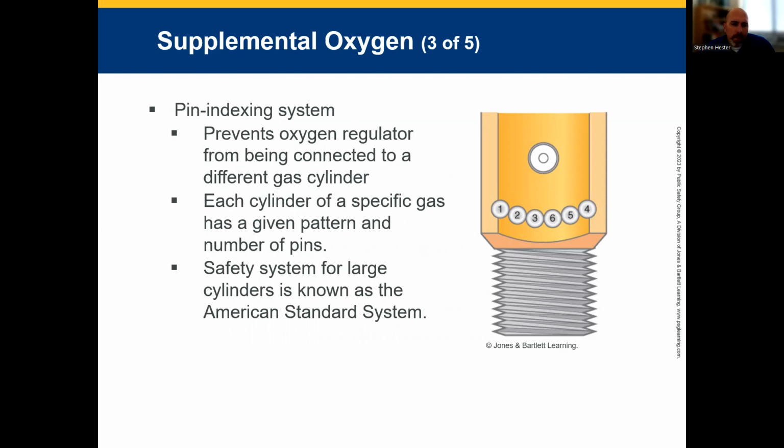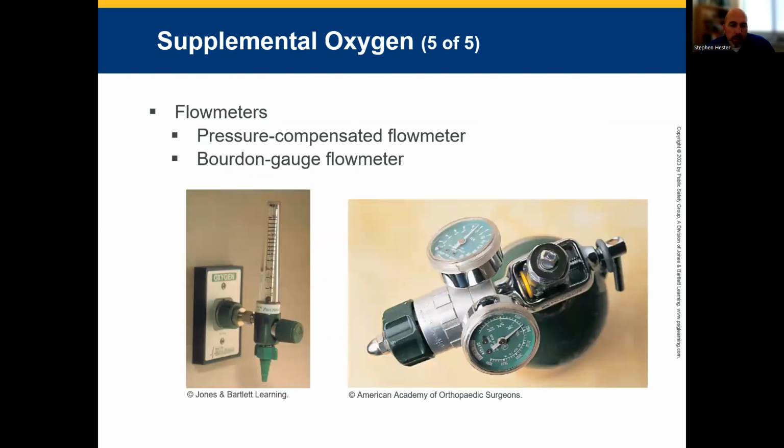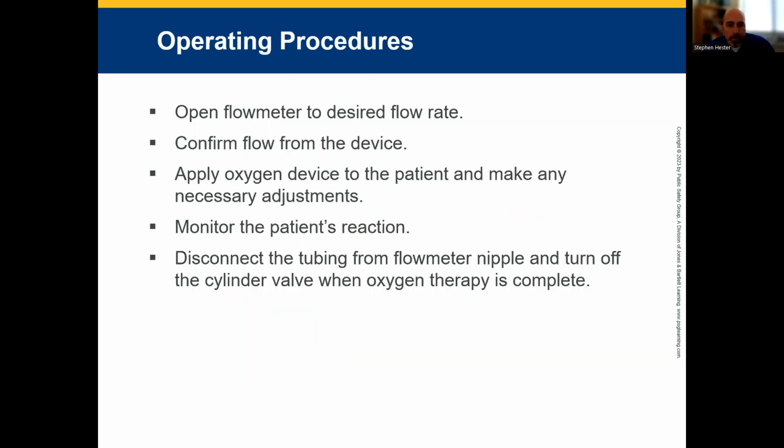The pin index system prevents an O2 regulator from being connected to a different gas cylinder. There's your pressure regulators, and there's the portable one and the wall mount. Okay, just some reviewing of how to open up an oxygen regulator or a tank itself.